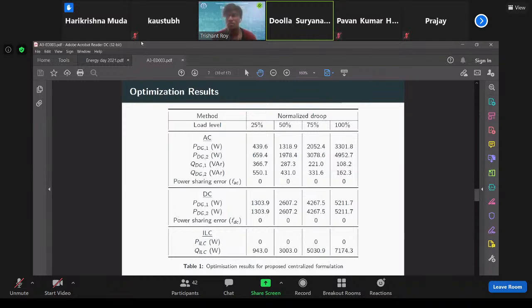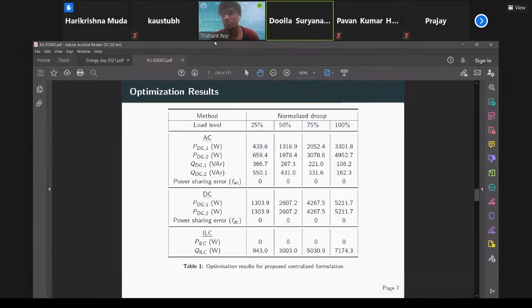I think it's also not a good idea to tell the interlinking converter not to supply any reactive power. The idea of the interlinking converter is that it should act like a transformer, allowing power to flow freely depending on the supply-demand gap. If I remember correctly, the original paper refers to the use of droop control in the interlinking converter, so depending on the voltage on one side and the frequency on the other, power will move from left to right and vice versa. So I don't think there are any plans to implement restricted power flow in this case.